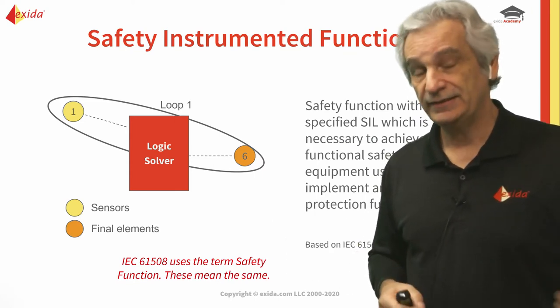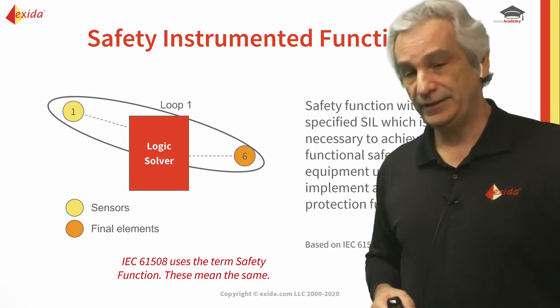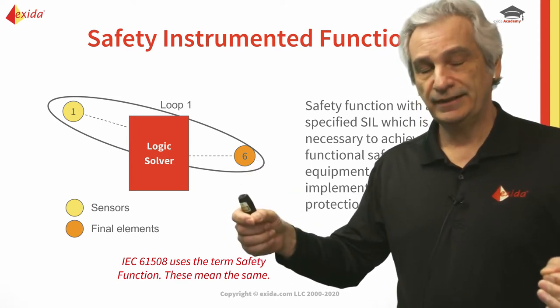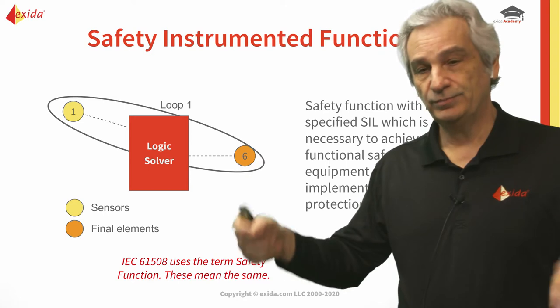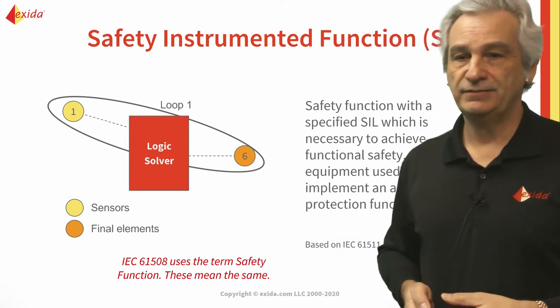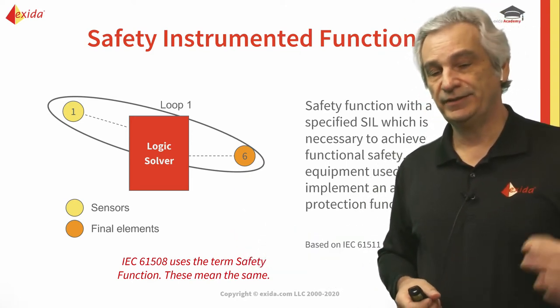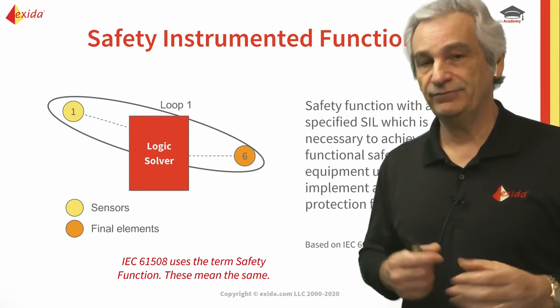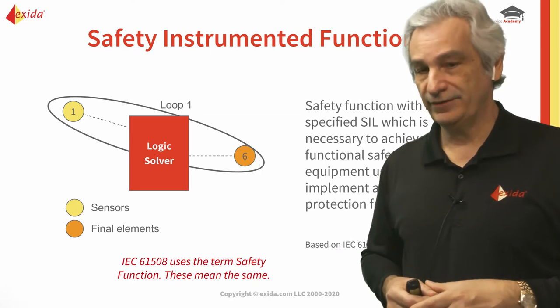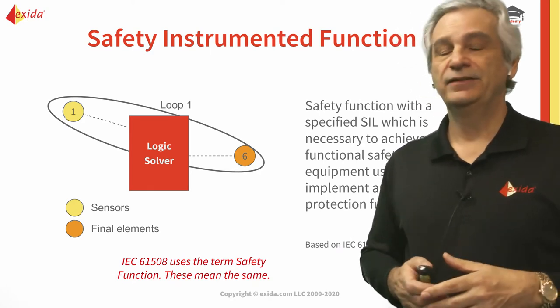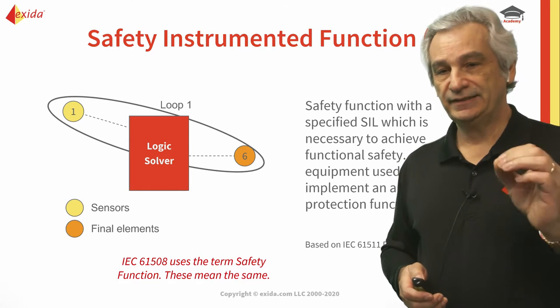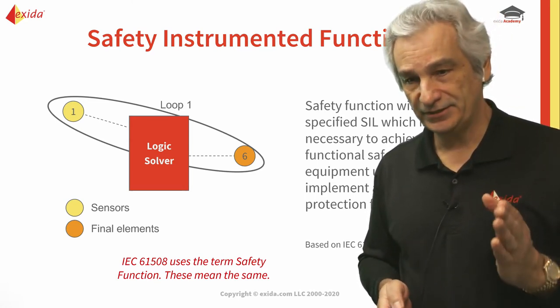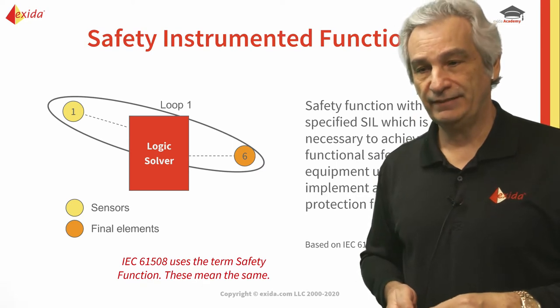So if it's a high pressure situation, it's a high pressure SIF — we need to detect the high pressure and we need to be able to take action to reduce that or bring us back to the safe state. The distinction between the SIS (the safety instrumented system) and the SIF (a single function) is very important, because it's that SIF that will have the designated safety integrity level — a specific SIL for that SIF.